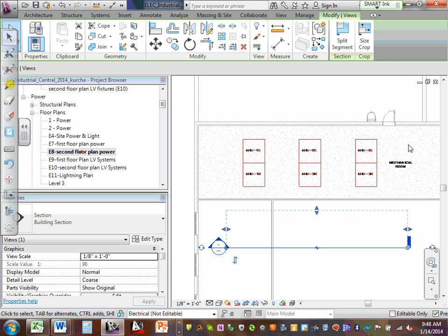Now, the mechanical code, not the fire code, the mechanical code says that all air handling units rated at 2,000 CFM or greater must have smoke detection to shut it down. Okay. We accomplish smoke detection on an air handling unit through a device known as a duct type smoke detector. Literally, it's a smoke detector that's installed on the side of the ductwork. It's got a tube that penetrates across the width of the duct on the inside. And if there's smoke in that airstream inside the duct, that smoke enters that sampling tube and passes that air through the detector itself, which is mounted on the exterior of the duct. And if it reaches, let's say, 3% per foot obscuration, boom, you get a supervisory signal.